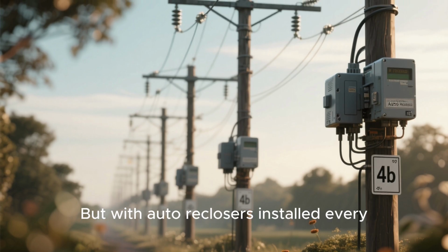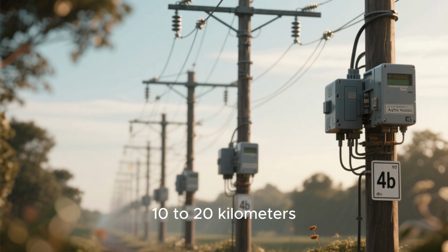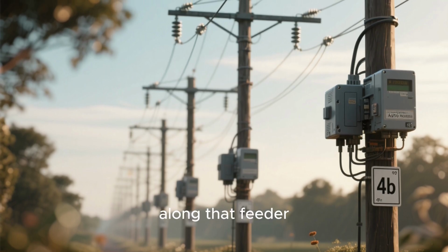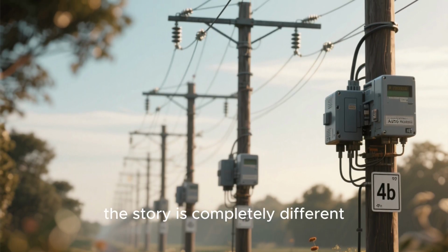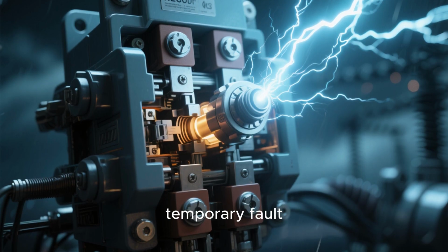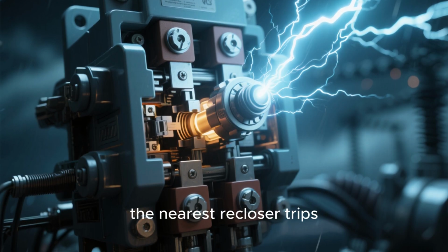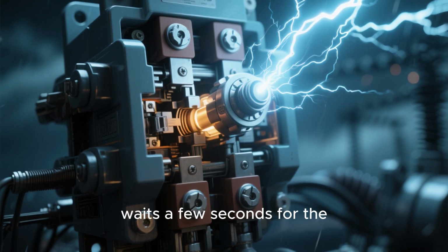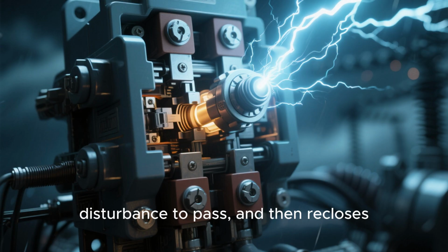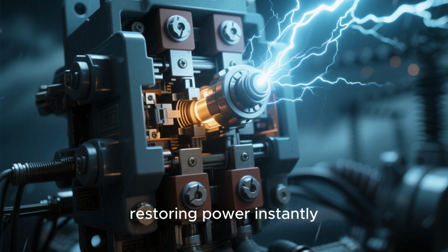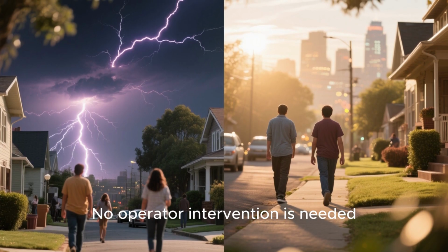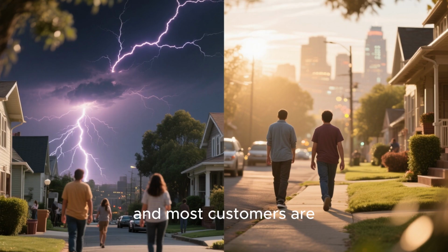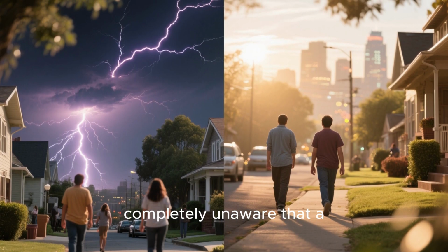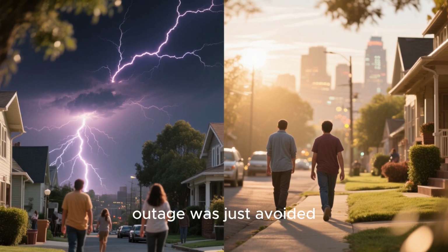But with auto reclosers installed every 10 to 20 kilometers along that feeder, the story is completely different. When the lightning strike causes a temporary fault, the nearest recloser trips, waits a few seconds for the disturbance to pass, and then recloses, restoring power instantly. No operator intervention is needed, and most customers are completely unaware that a potential long-term outage was just avoided.